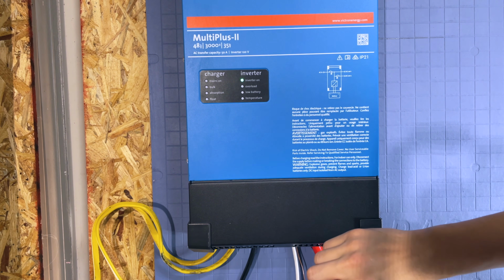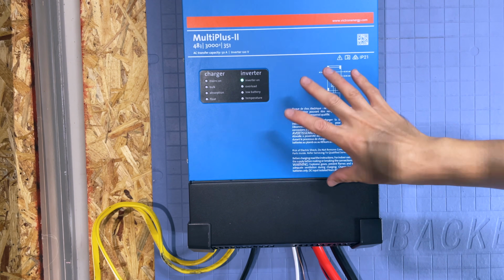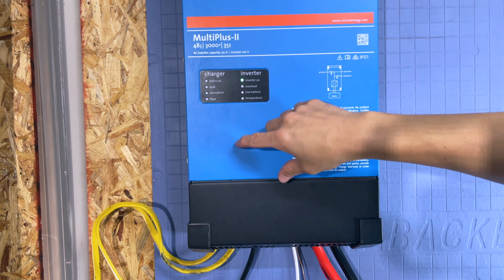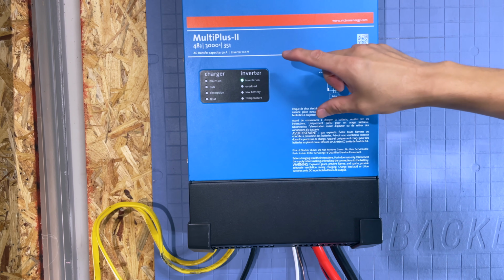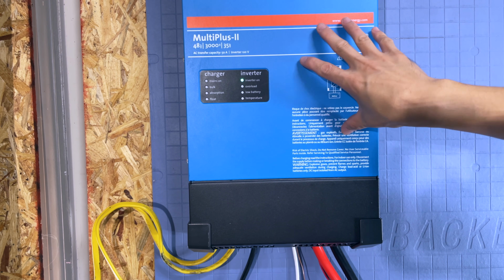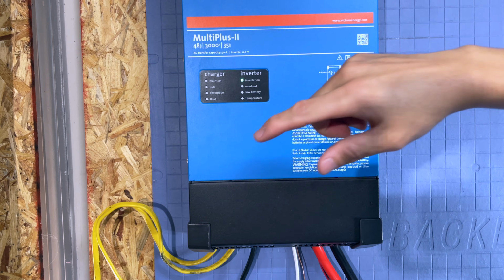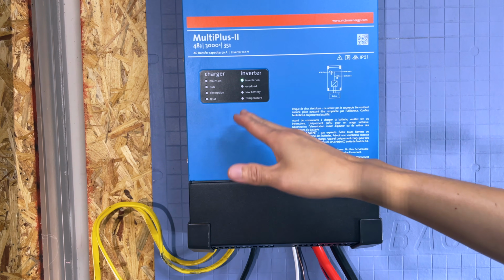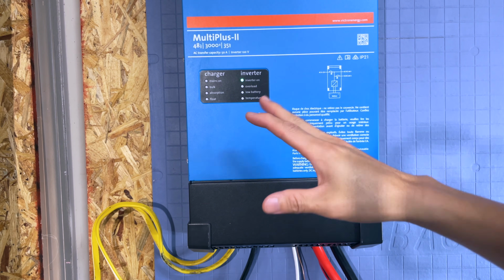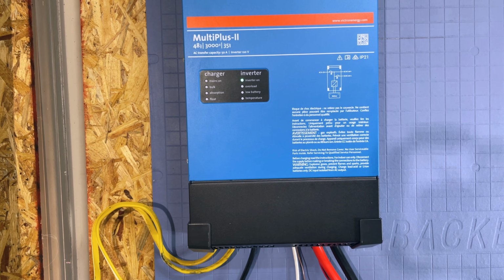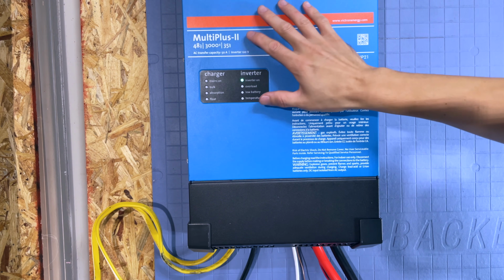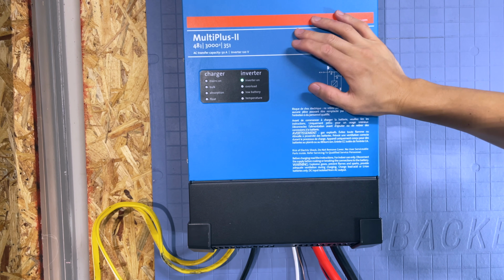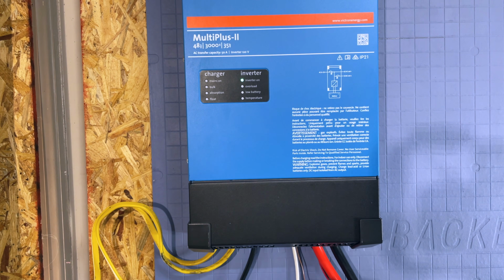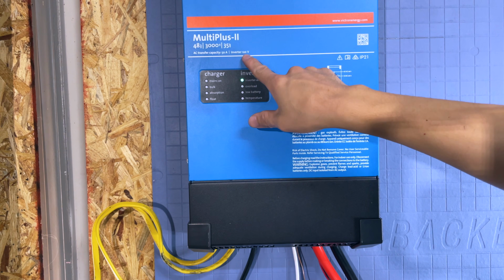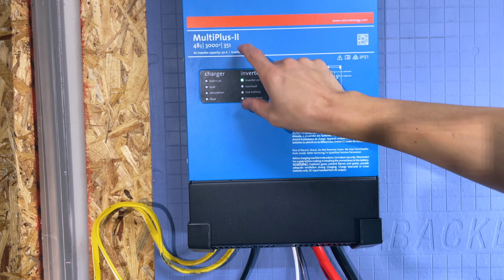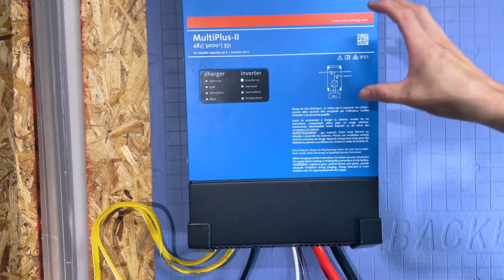Let's talk a bit about the basic capabilities of this inverter. The feed-through current maximum is somewhere around 32 to 35. The voltage range of the 48 volt system is somewhere between 38 to 66 volts, so it doesn't have to be exactly 48, but somewhere in there, with 48 being the sweet spot. The output voltage of this inverter is 120 volts. It is a single phase, low frequency, transformer-based inverter.